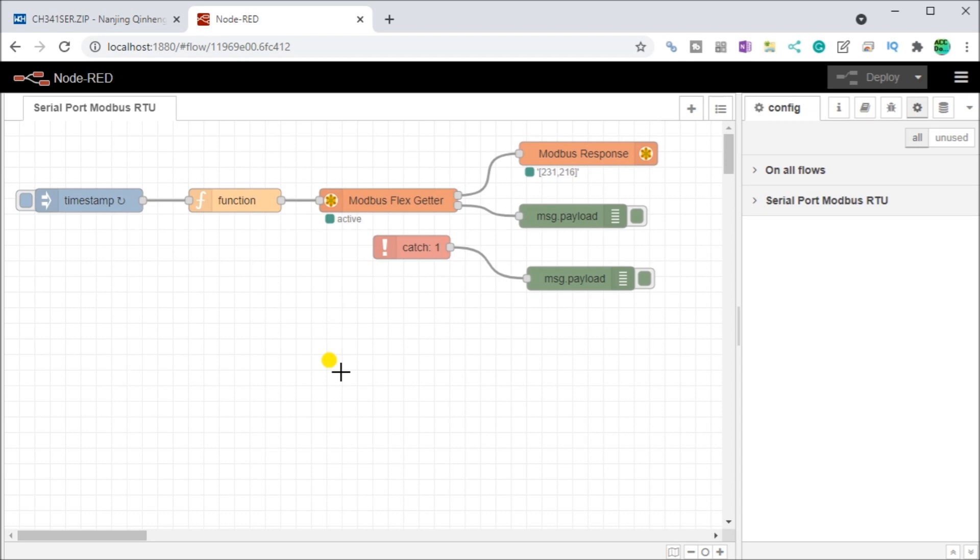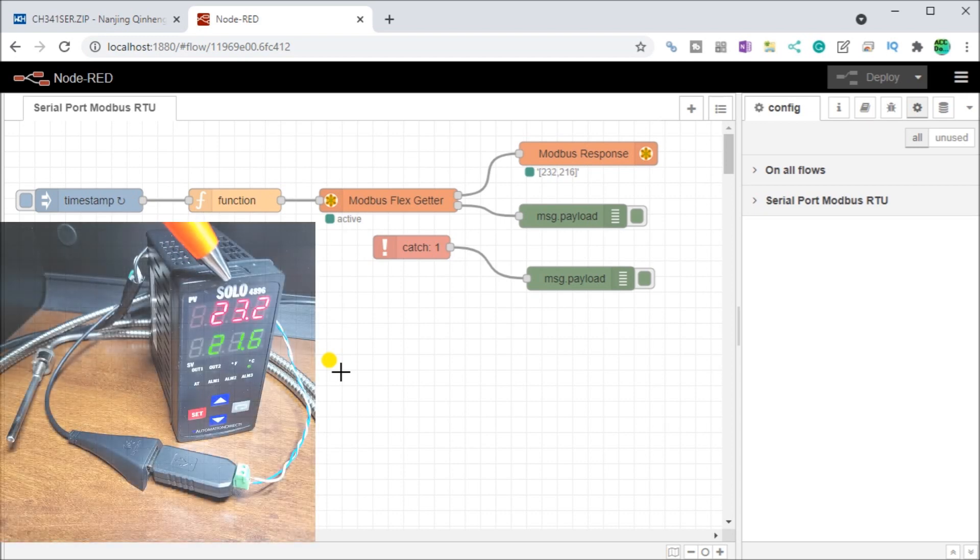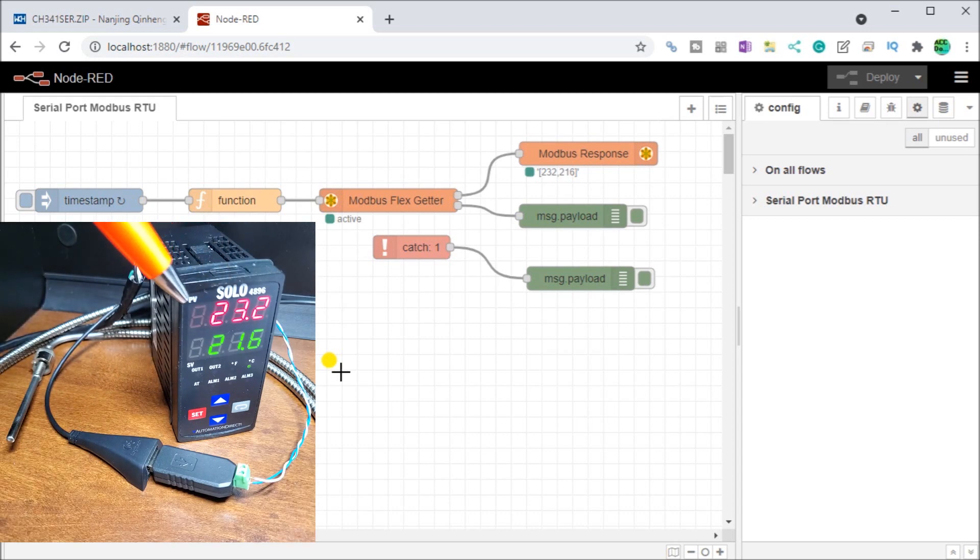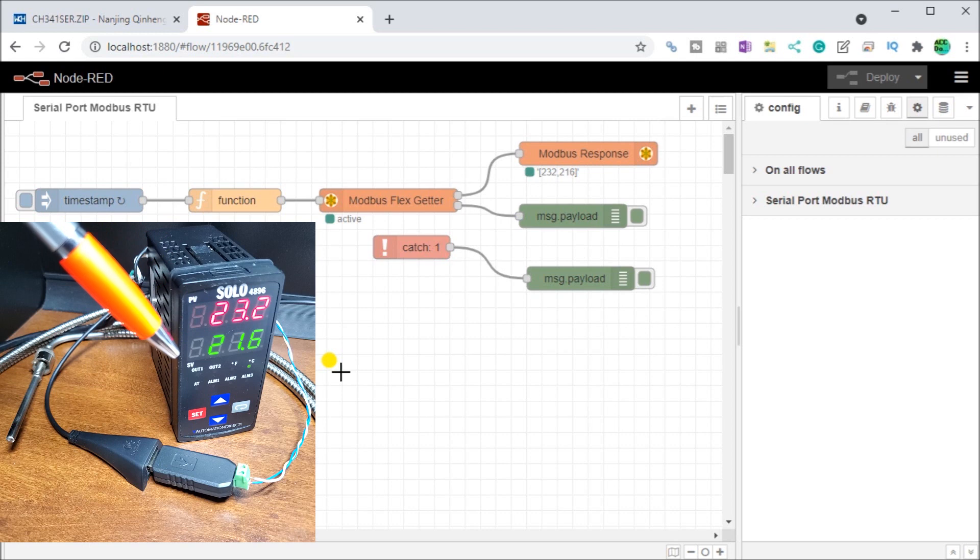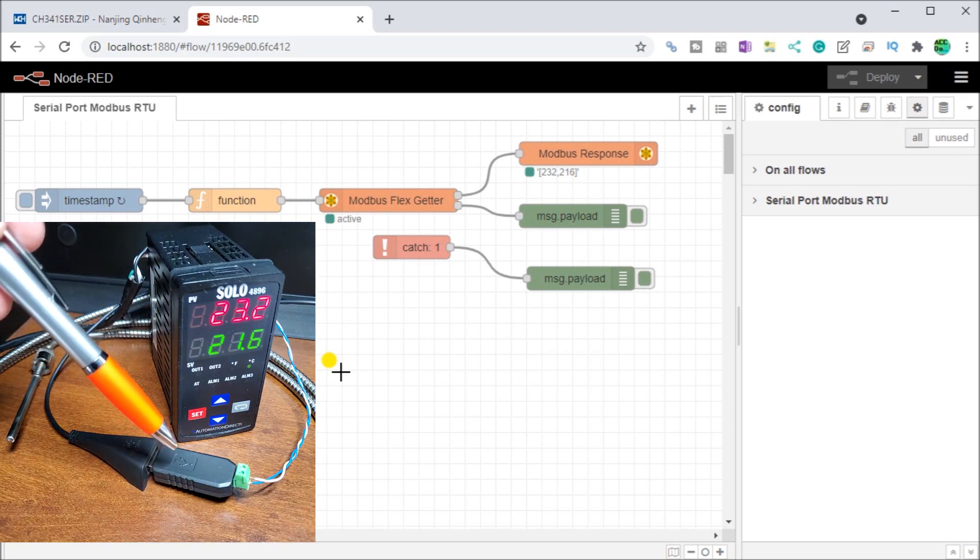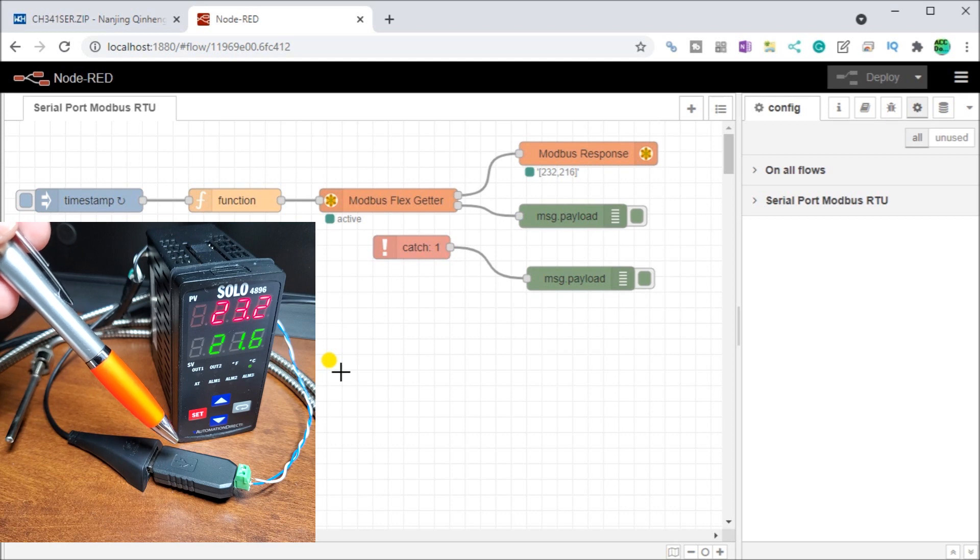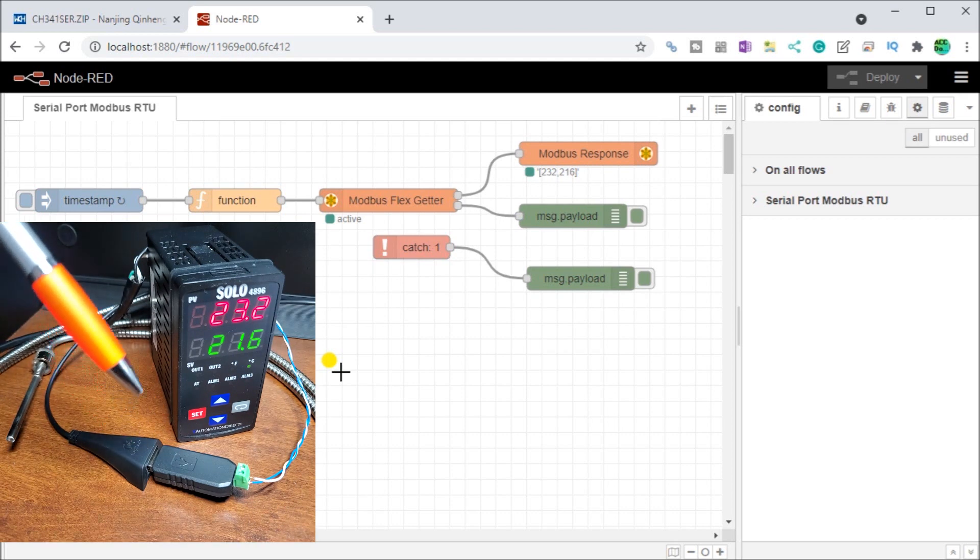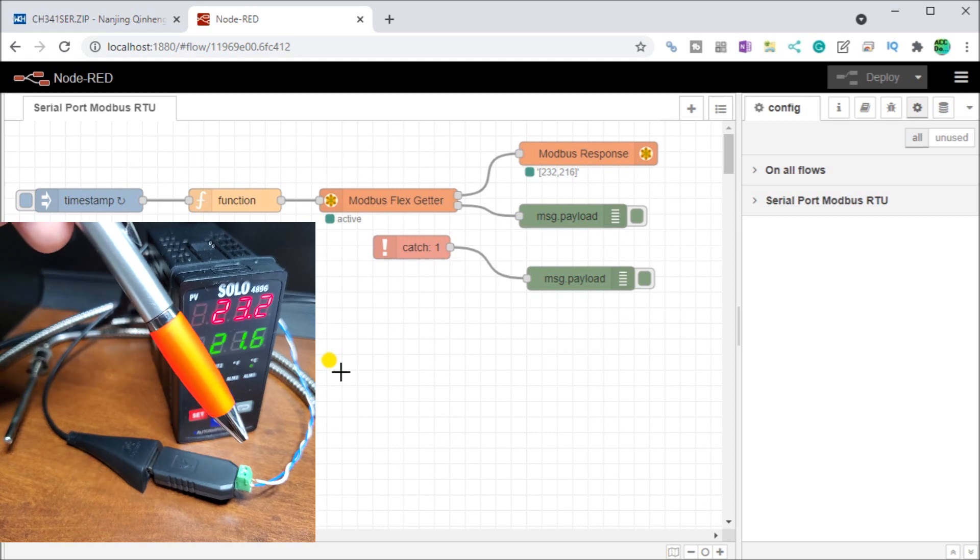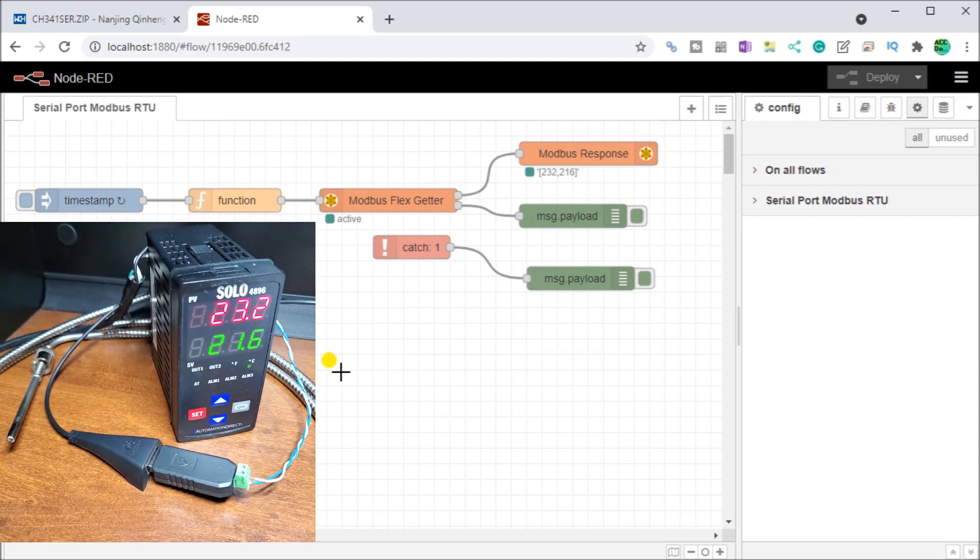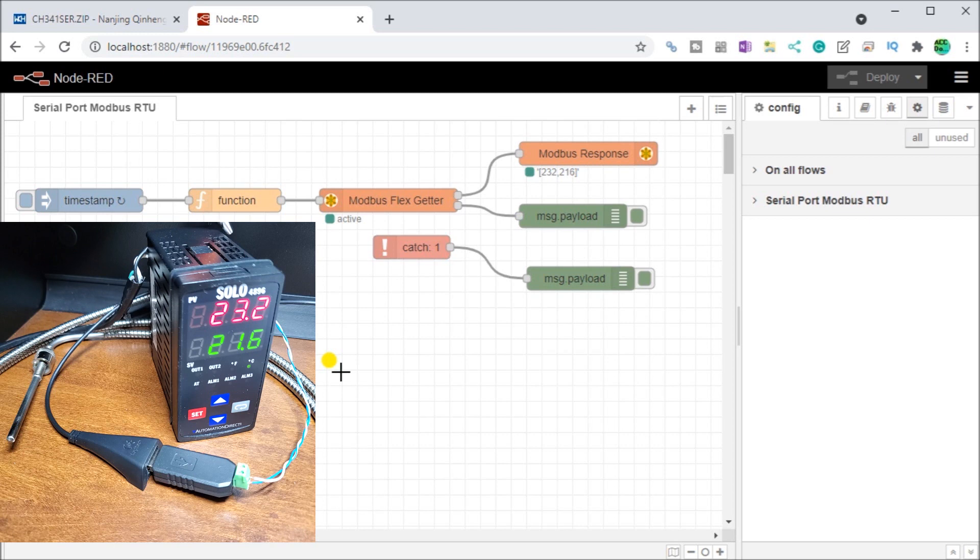Now let's just look at our actual hardware. So here is our solo process temperature controller. It's the model 4896. And there's my present value and my set value. And here is my adapter, my USB adapter, and we are connected through our USB port on our computer. And on the other side of the adapter through the screw terminals, we are connected back into the solo through the Modbus communication port right here, RS-485.